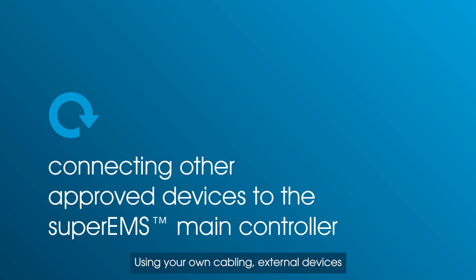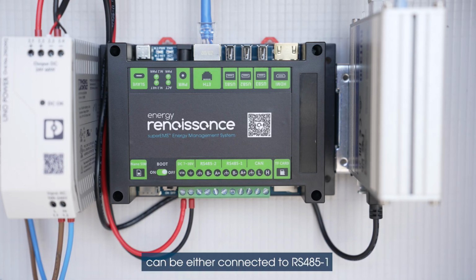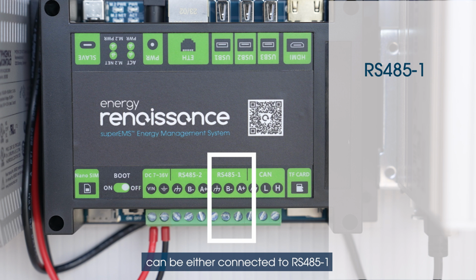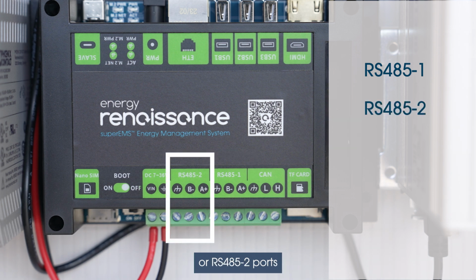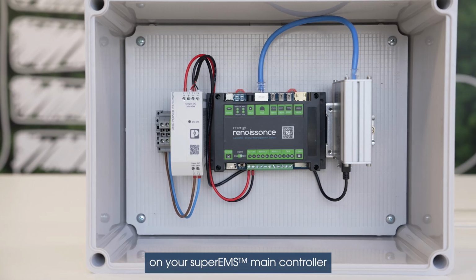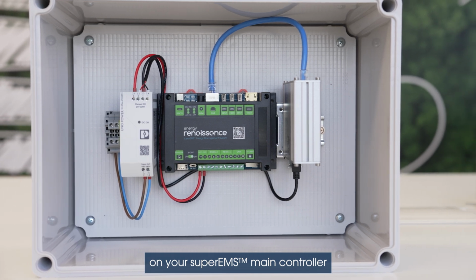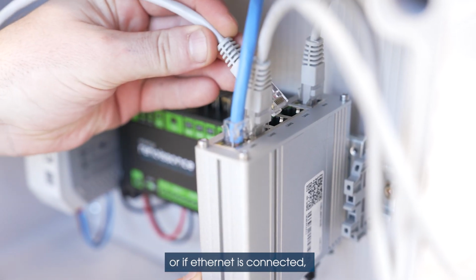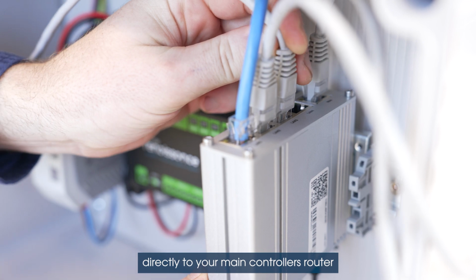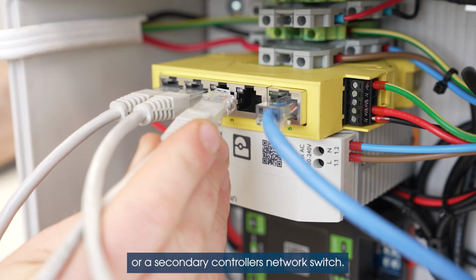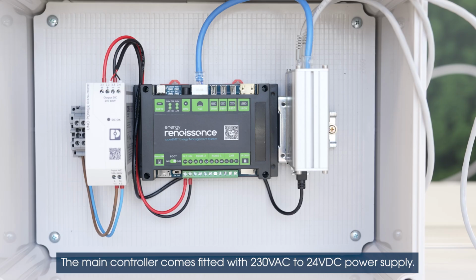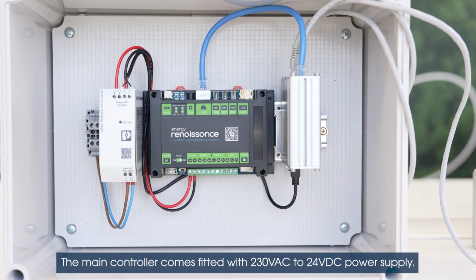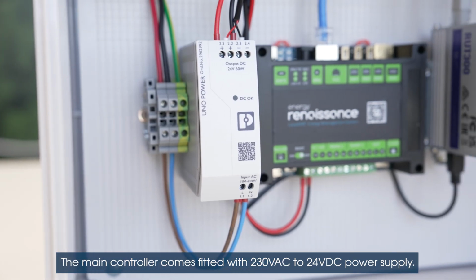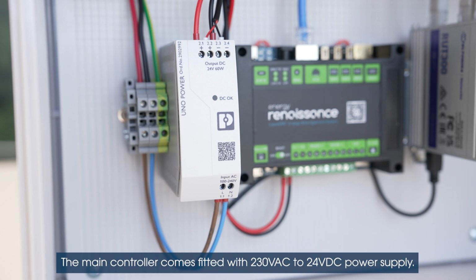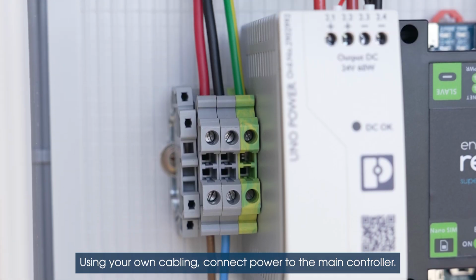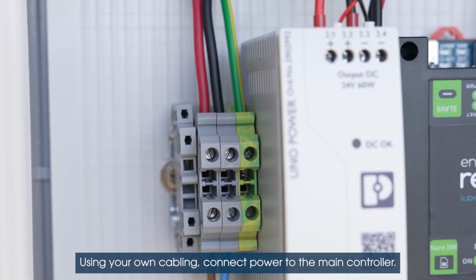Using your own cabling, external devices can be either connected to RS485-1 or RS485-2 ports on your superEMS main controller, or if Ethernet is connected, directly to your main controller's router or a secondary controller's network switch. The main controller comes fitted with 230 volt AC to 24 volt DC power supply. Using your own cabling, connect power to the main controller.